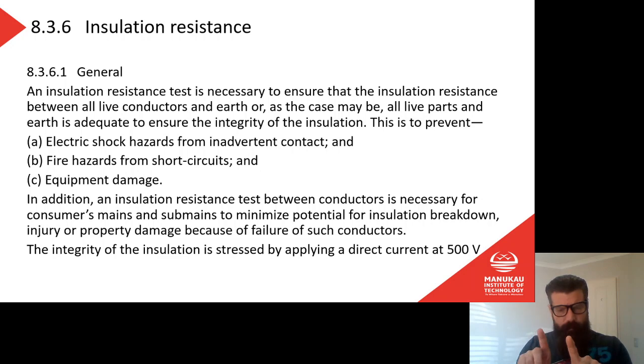What we're going to do is put a voltage on the red wire and a voltage on the black wire. We use a special meter to do this called an insulation resistance tester. I put a voltage on each of them, and if there's any touching between the red and black wire, then the insulation resistance tester is going to show me that there is a circuit. Just like we did with the earth continuity, but this is the opposite. When we do earth continuity, we want a circuit. It has to be a very low resistance. With insulation resistance, I'm testing between 2 wires that shouldn't be touching, and so therefore I should find that there is no circuit.